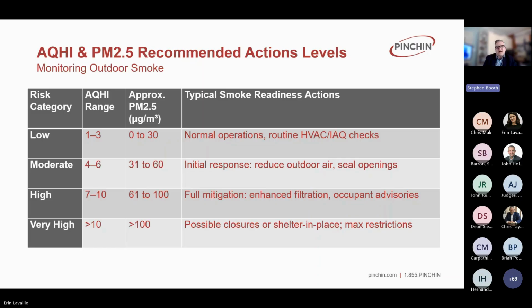Each of those levels can trigger different actions. In the low range, run the building as normal. Once you get into moderate, you might reduce outdoor air coming into the building, seal up some openings, and for apartment buildings with operable windows, advise keeping windows closed starting at moderate. At higher levels, bring in additional precautions like occupant advisories or enhanced filtration. At very high levels, you may look at dedicated clean air spaces within the building, relocating occupants, or suggesting people not come into work those days. So those are the levels of action required, and roughly how AQHI and PM 2.5 concentrations correlate.